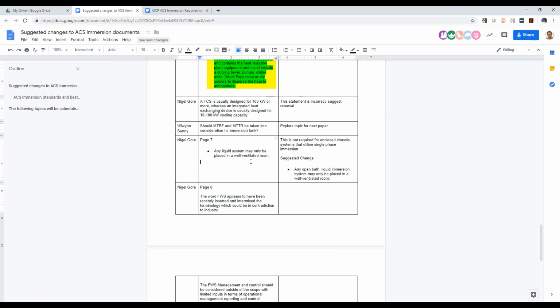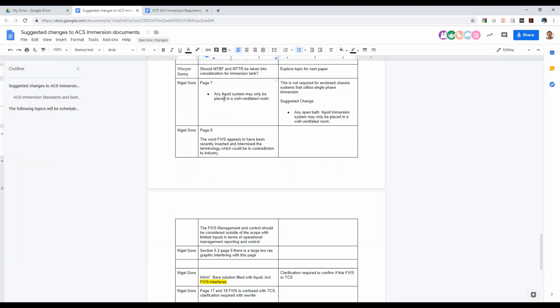Nigel: any liquid system may only be placed in a well-ventilated room. This is not required for enclosed chassis systems that utilize single-phase immersion. Suggested change: any open bath liquid immersion system may only be placed in a well-ventilated room. Does anyone want to comment? I tend to agree. Does anyone object to this change? No, I don't, I agree with it.